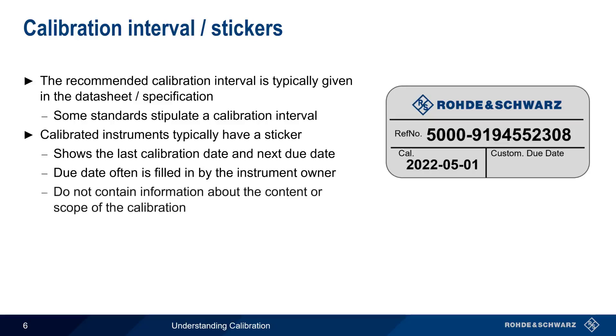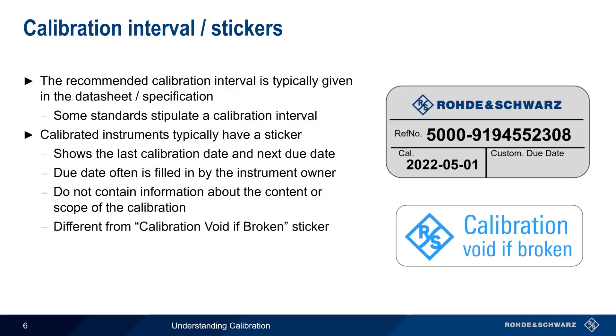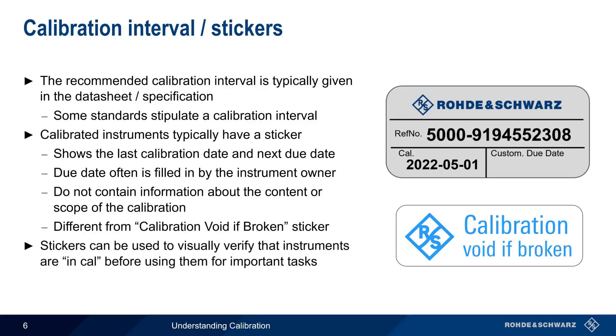However, these calibration stickers do not contain any information about the content or the scope of the calibration. Also note that these are different from the 'calibration void if broken' type stickers, which are used to discourage unqualified persons from opening up an instrument. Both of these types of stickers are important in that they provide a quick visual check as to whether the instrument is still in cal before using it for important tasks.